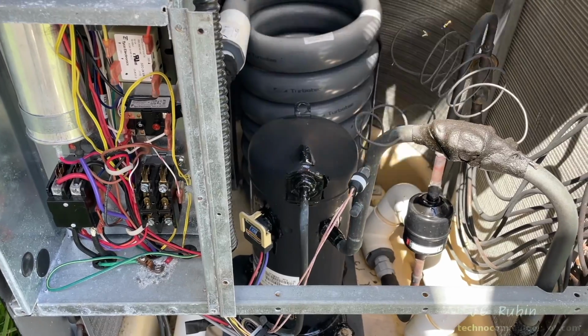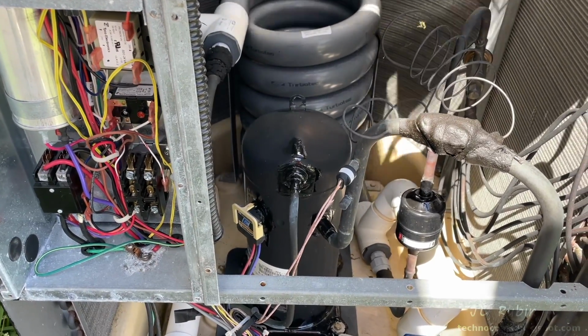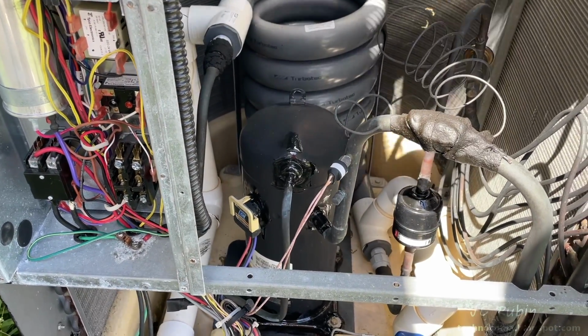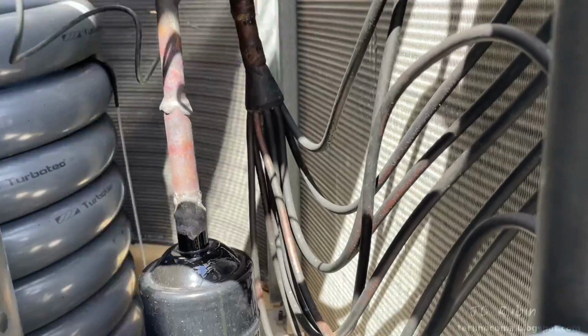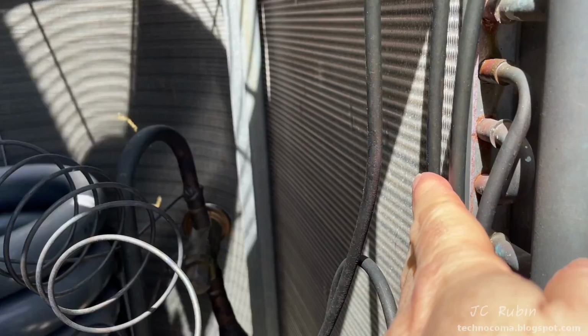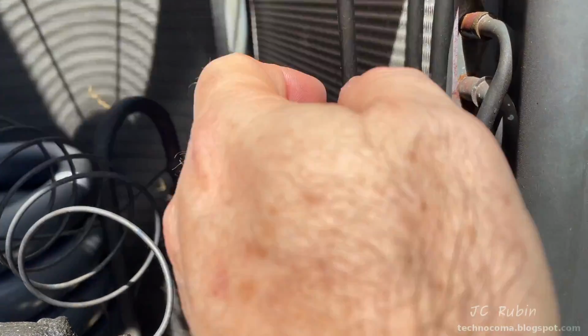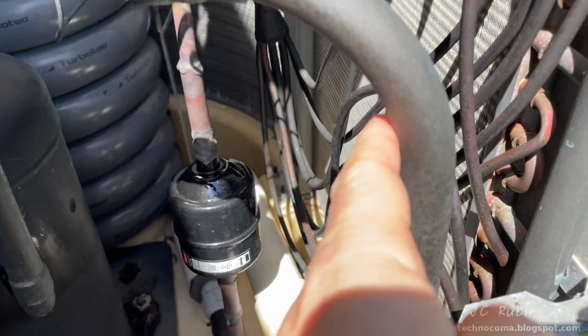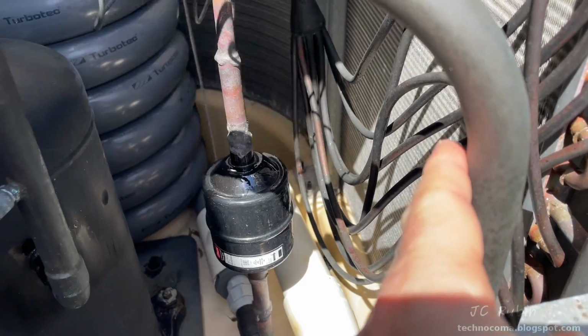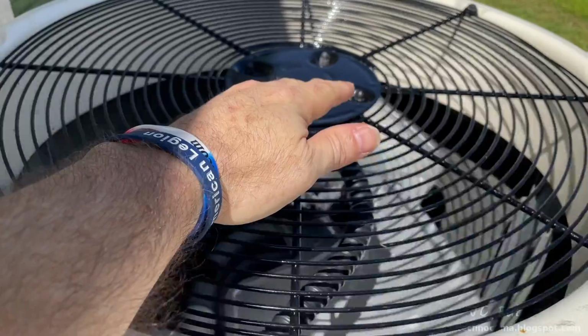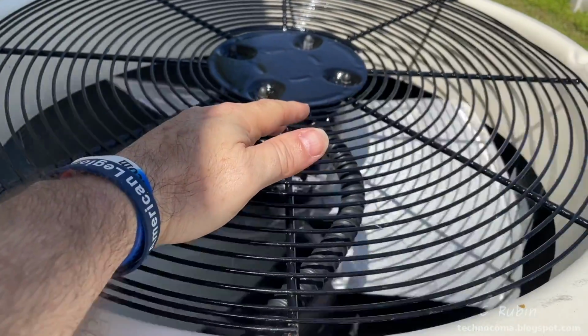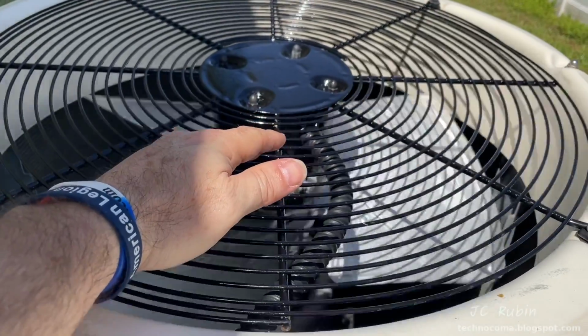Everything sounds good from the compressor, I don't hear any strange noises, nothing that concerns me. It will not, however, cool properly with this cover open, though I do feel the change in temperature on these pipes is a good sign. Also on the heat exchanger, it's starting to get hot, though it will always run inefficient until it's closed up. Most of this air is going to pull from the path of least resistance when that front cover is open.